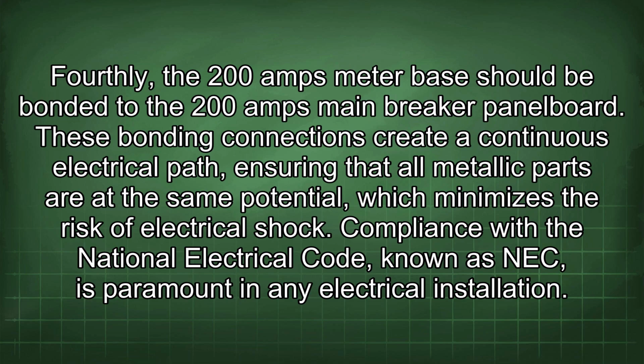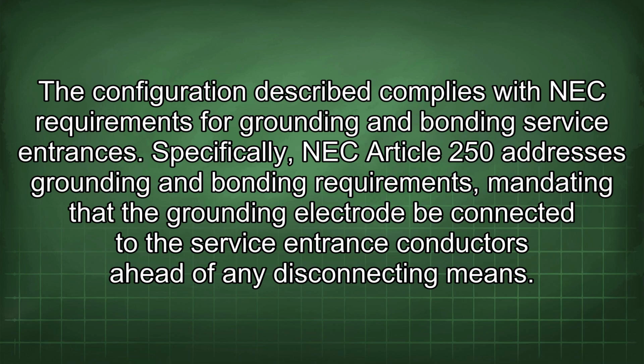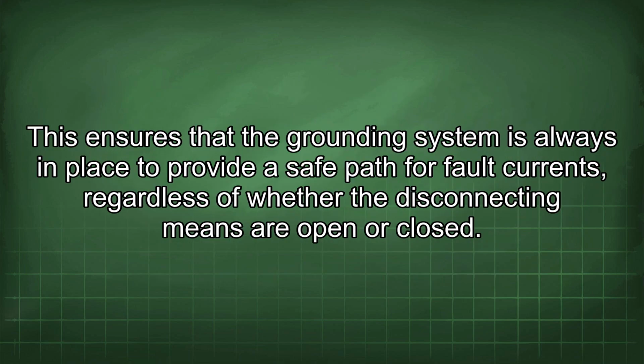Compliance with the National Electrical Code, known as NEC, is paramount in any electrical installation. The configuration described complies with NEC requirements for grounding and bonding service entrances. Specifically, NEC Article 250 addresses grounding and bonding requirements, mandating that the grounding electrode be connected to the service entrance conductors ahead of any disconnecting means. This ensures that the grounding system is always in place to provide a safe path for fault currents, regardless of whether the disconnecting means are open or closed.